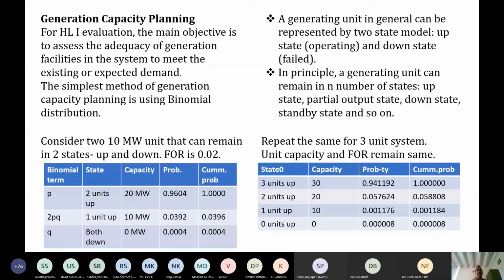And this is for a 2-unit system. Similarly, if we have a 3-unit system, the forced outage rate remaining the same, we again get a similar thing: 30 megawatt with this probability, 20 megawatt with this probability, 10 megawatt with this probability, and 0 megawatt with this probability. You can see, if your load is only 10 megawatt, the probability of getting that 0 megawatt generation condition is very low. It's 0.000008, so I can say this is 8 into 10 to the power minus 6. That is a very, very low probability that we will have no generation at all. If our demand is 10 megawatt only, then this system is highly reliable.